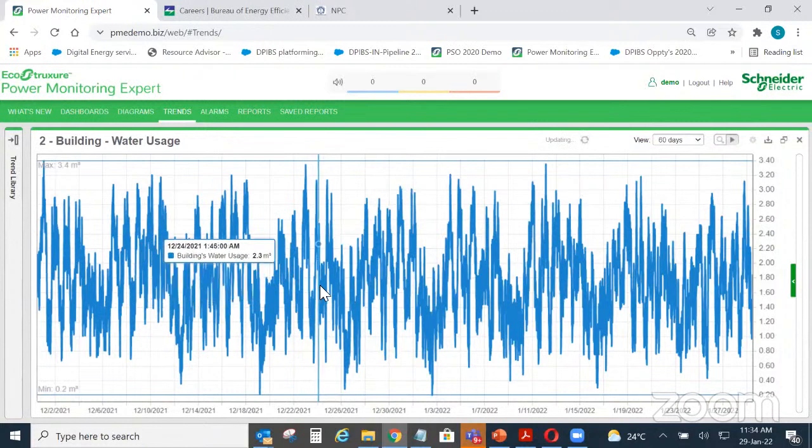Okay, so you can see here in the night time also the water usage happening, very excessive water usage. This is how we can see the opportunity where some optimization can be done here. So you can see 10:15 p.m., early morning 1 a.m., 10:45 a.m., 7 a.m. You can see some water usage happening in the night, midnight 2 a.m., 5 a.m. and all. So this is how we can get the analytics here.